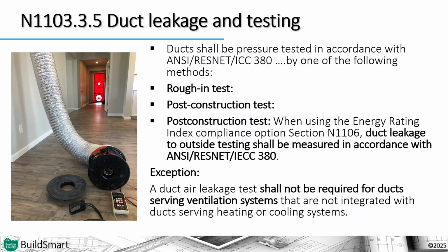Regardless, for the BuildSmart code, using the HERS Energy Rating Index compliance alternative, you will have a duct leakage to outside test at final in order to produce the final confirmed energy modeling and compliance reports. Whole house controlled mechanical ventilation duct does have to be air sealed, but there is no requirement to test that duct unless the duct is integrated with the duct servicing the system that is heating and cooling the house itself.